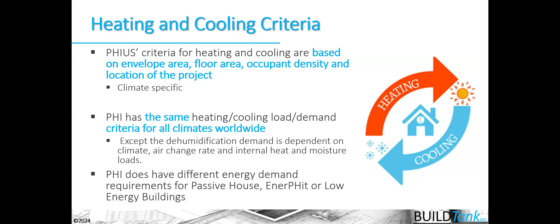One question this brings up is how do we integrate HVAC design and the IECC HVAC design criteria into Passive House? Passive House doesn't do HVAC design in accordance with ACCA standards. They do calculate heating and cooling loads, similar to Manual J, but how equipment is selected to meet that capacity, and how ducts or distribution systems are designed, isn't really in alignment with how the code does things.